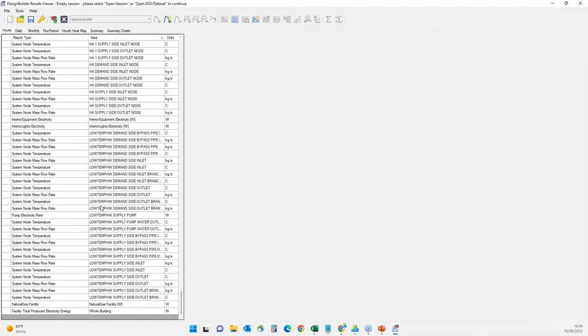The run is complete. My initial observation is that on the systems load graph, heating is happening regularly and being supplied to the zone. However, on the fuel graph, I can see that the electricity used for heating modulates a lot, meaning the boiler is switching on and off. Looking at the results in Results Viewer with the additional outputs I requested: the schedule value 'boiler control' shows the boiler is cycling in and out. As we have six time steps per hour, the fractional values represent the average of every 10-minute interval.